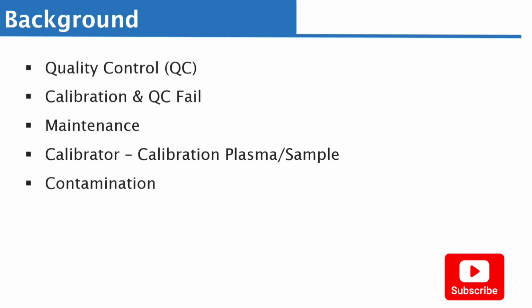All you need to do is to tell the analyzer, I want to do maintenance. And in most cases, it will tell you what to do step by step. Now, in order to do calibration, the same way you have your patient sample or control sample, you now have what you call a calibration sample, which is a calibrator. So you have calibration plasma or calibration sample as the case may be. So that is just to give you a background. I hope that makes sense.